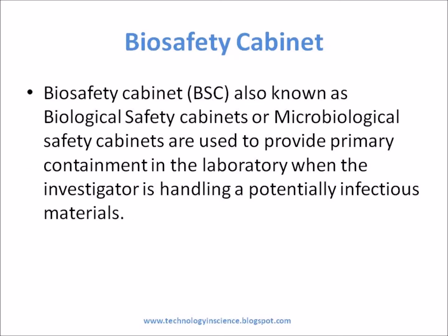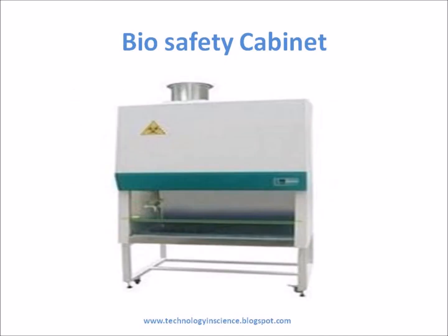Biosafety cabinets, also known as biological safety cabinets or microbiological safety cabinets, are used to provide primary containment in the laboratory when the investigator is handling potentially infectious materials. Biosafety cabinets are used to protect the laboratory worker handling infectious materials and also to protect the environment. Most biosafety cabinets also provide product protection. It is not safe for the user to work with pathogenic organisms in a laminar flow chamber.